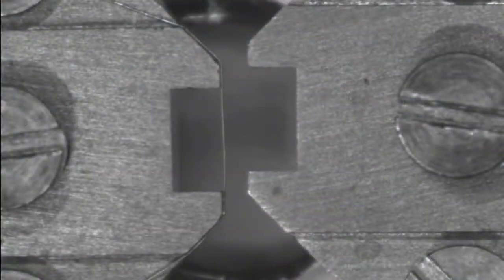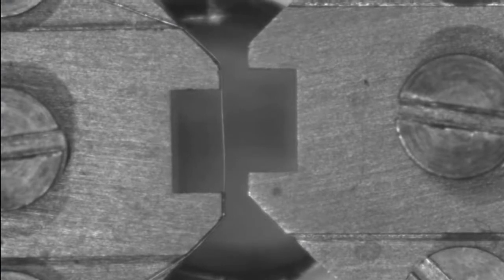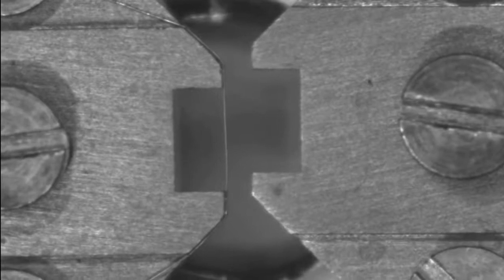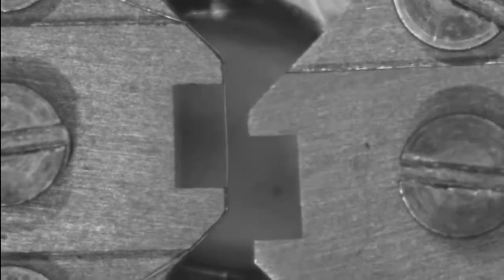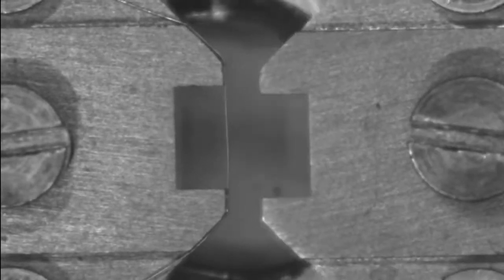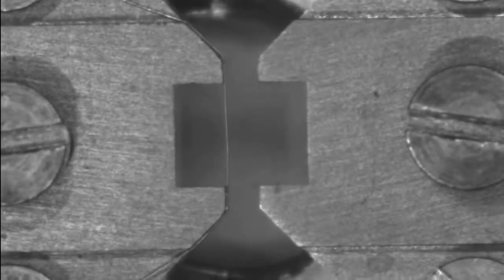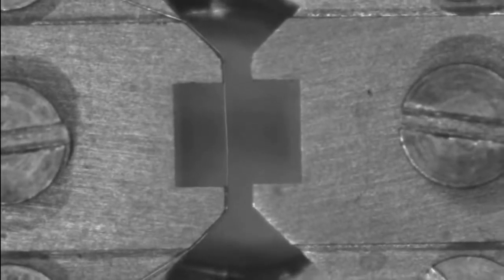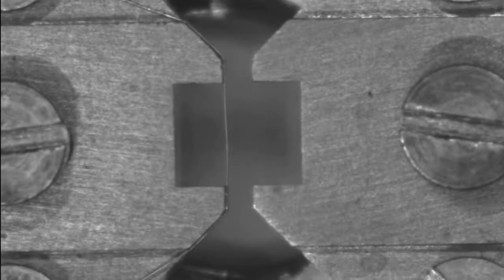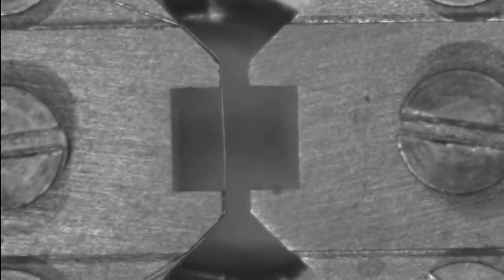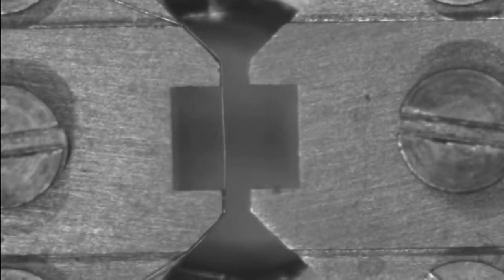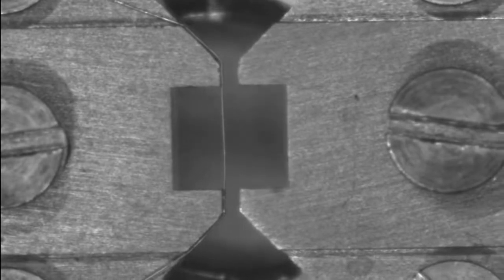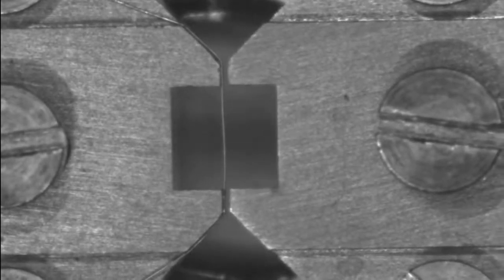In this instance, the far chamber was misaligned. We will start with a coarse adjustment using the ball-end screwdriver. By loosening this, we can get the jaws roughly to the same alignment. By then moving the jaws close together, you can see if they touch at the same time on both sides.